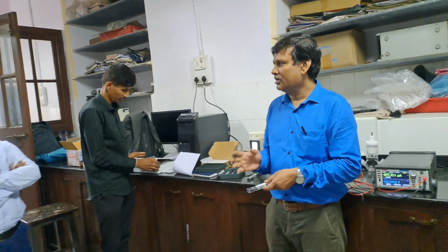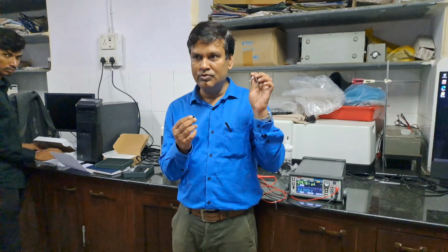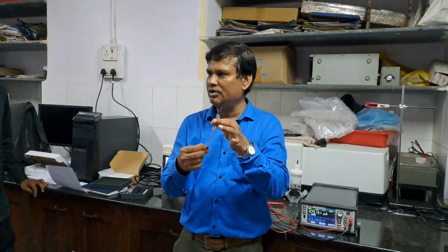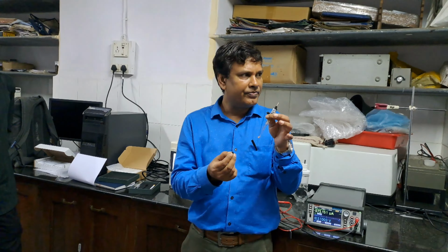Okay, and there is a way of filling it. When you use it, you have to remove this cap. Usually the cap is like this. You always should put this cap back after using it. After using it, you will wash it with distilled water, and you should put this back because this frit, this is called frit, this is porous. This frit should not get dry. If you have a very tightly airtight cap, then this will make sure of that.